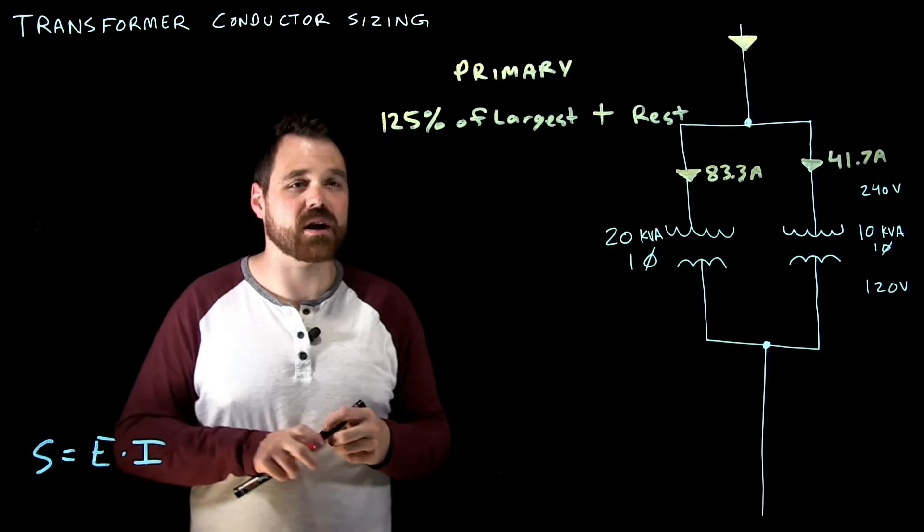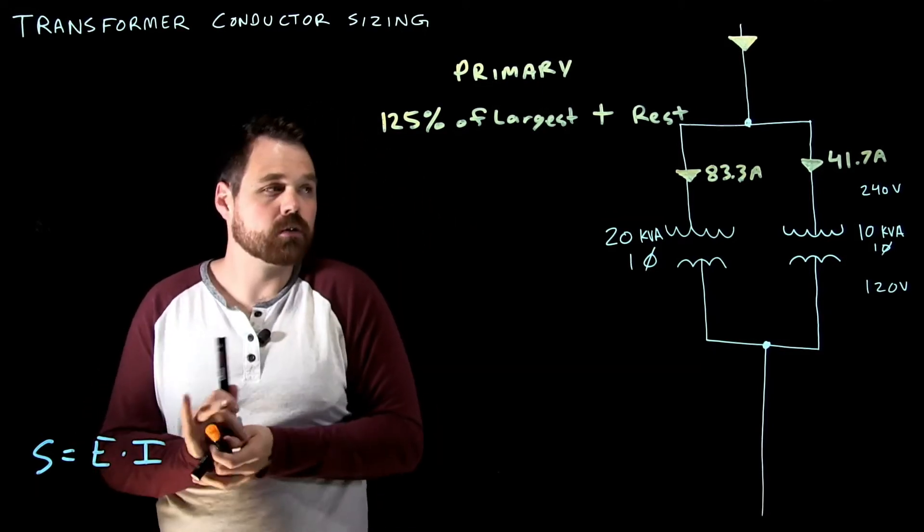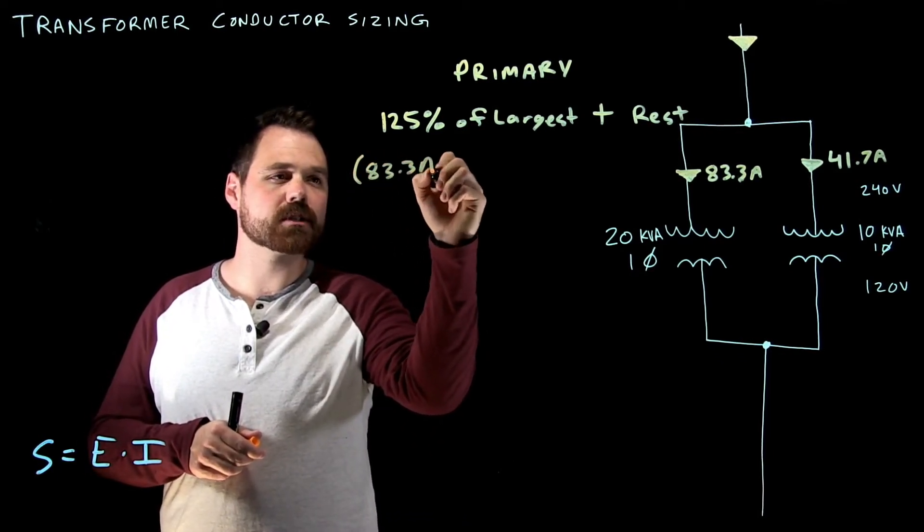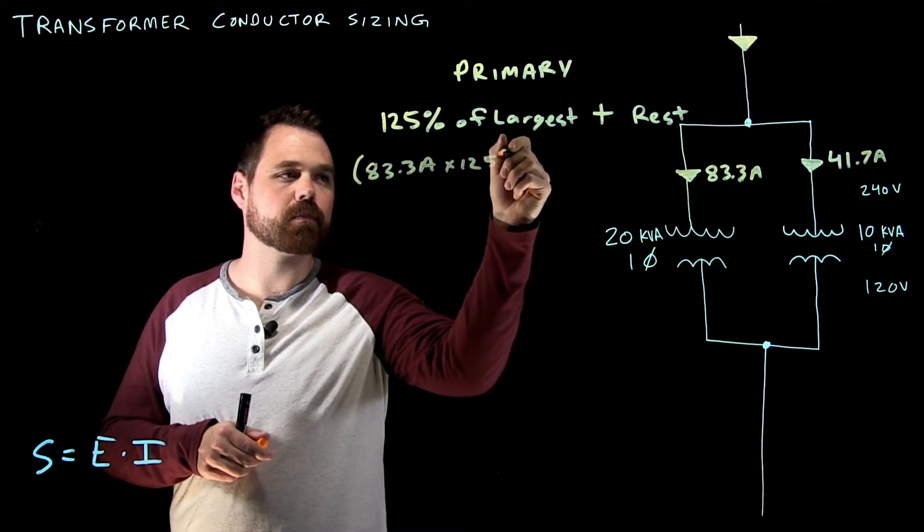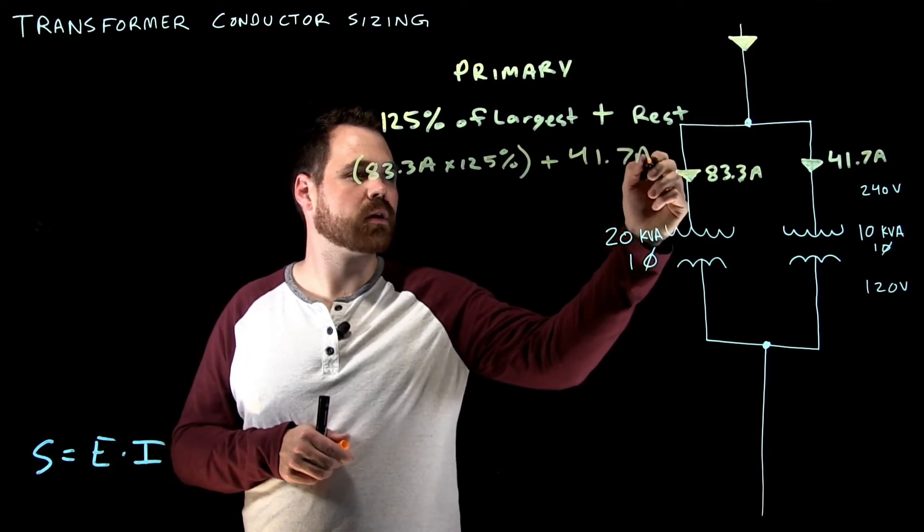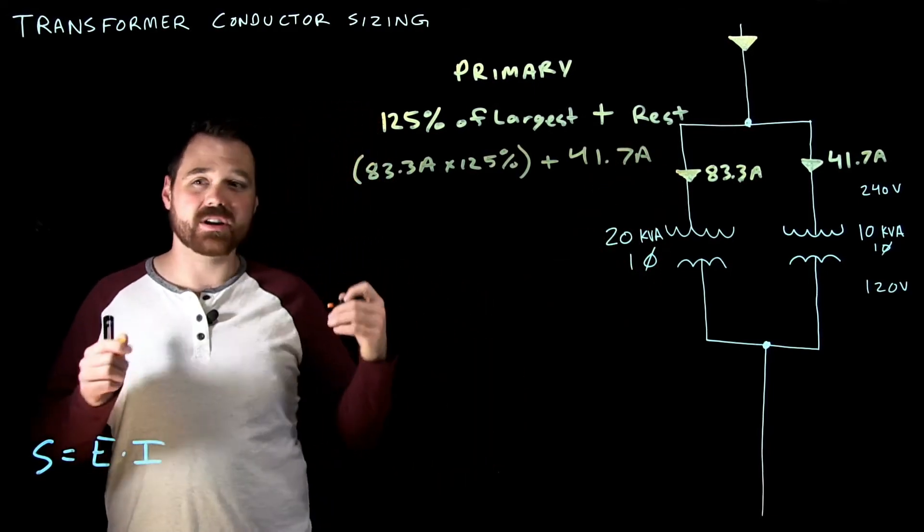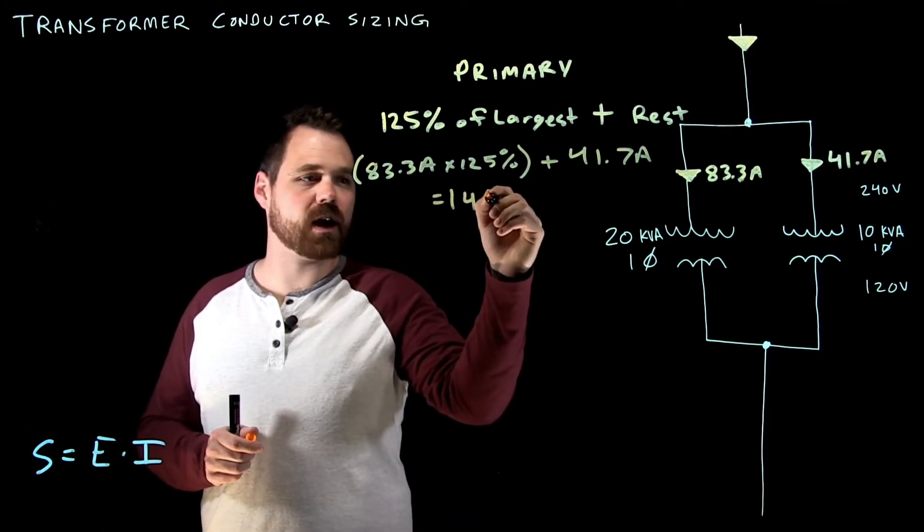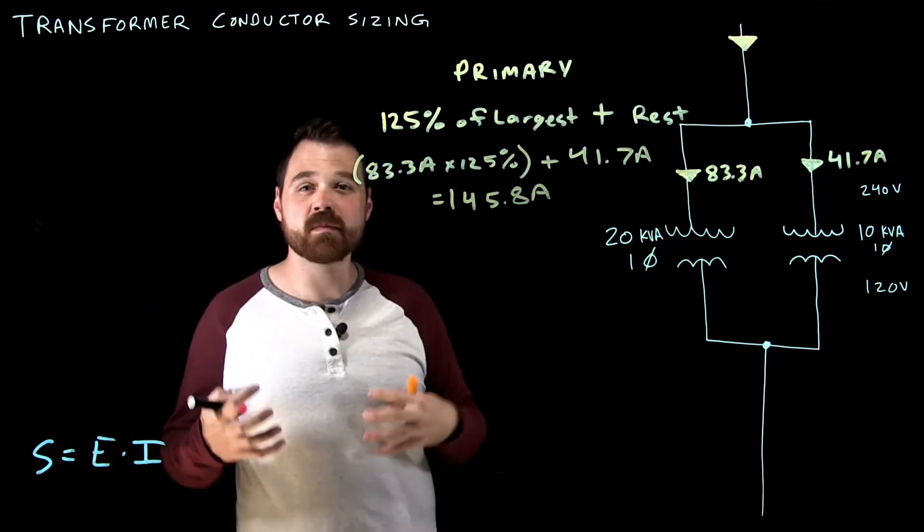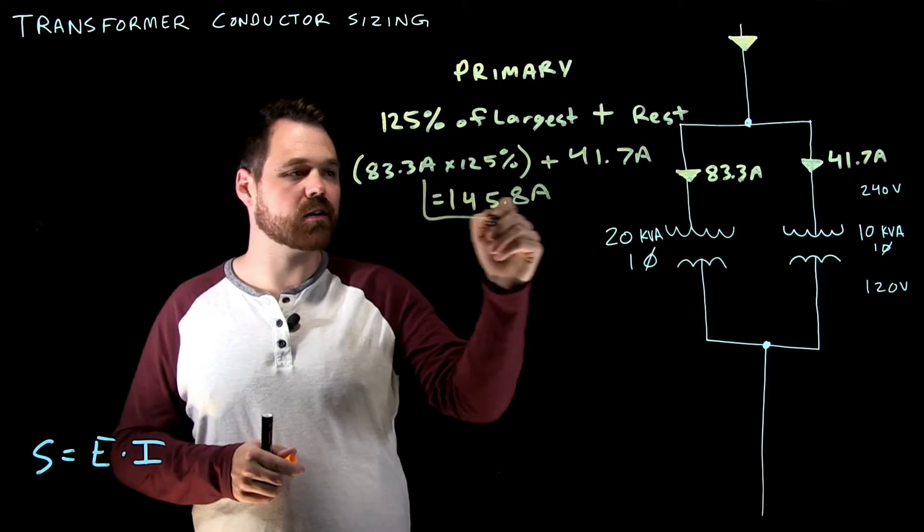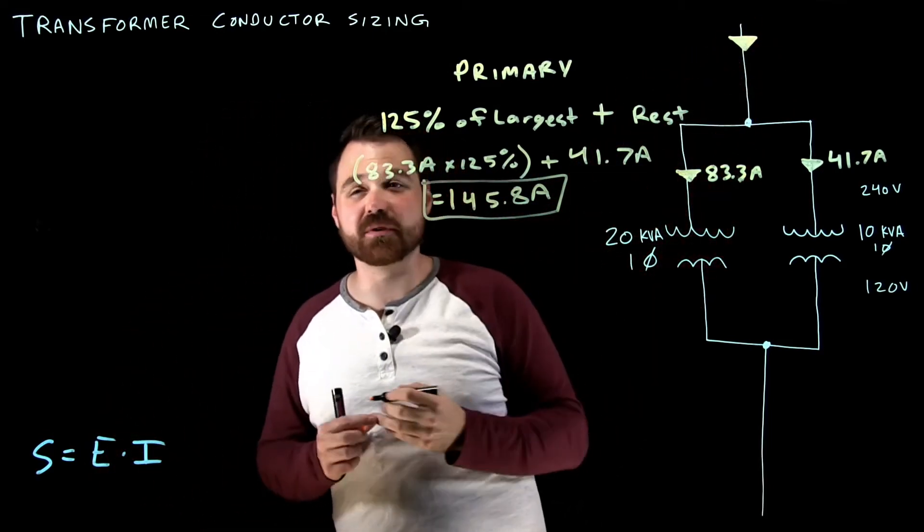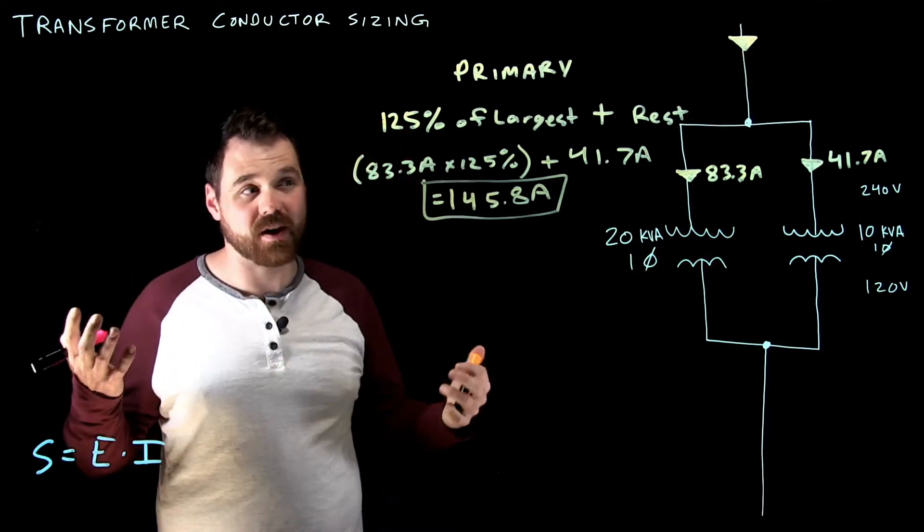Now in order to do this calculation, I'm going to go 83.3 amps times 125% plus 41.7 amps. That now is going to give me, I get 145.8 amps. That is the rating or the minimum required ampacity of my conductor up here. So when I'm sizing this conductor, it needs to be good for 145 amps, 145.8 amps.